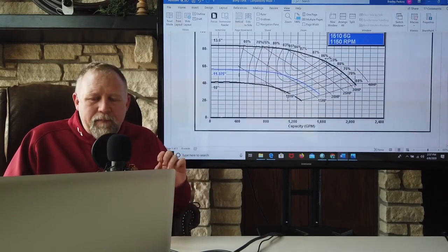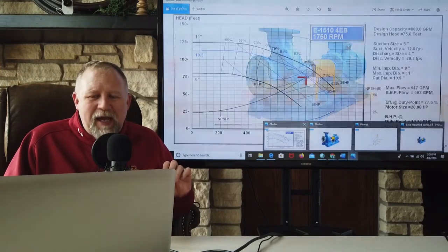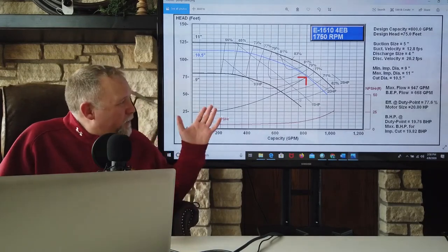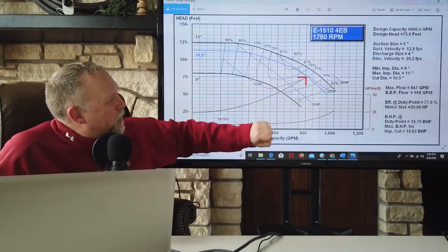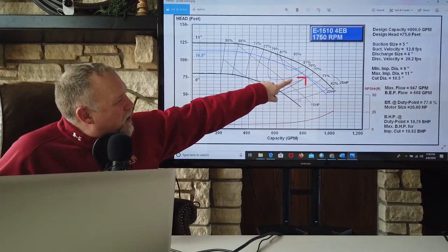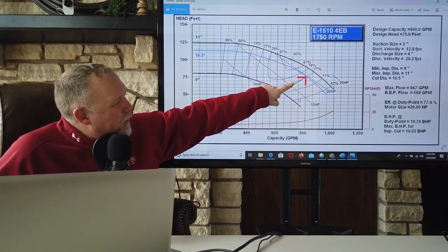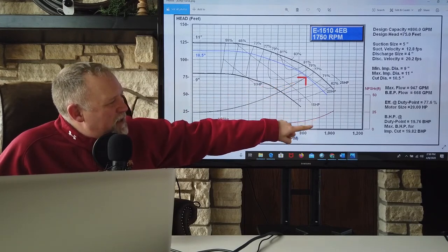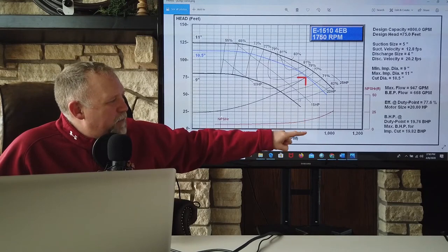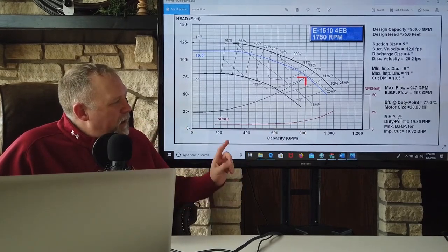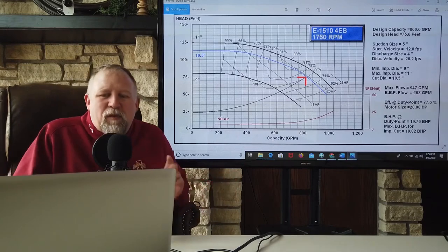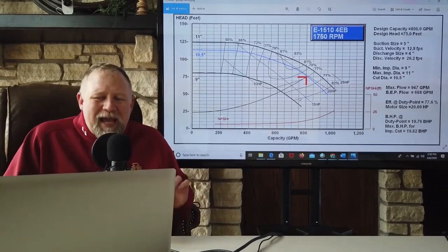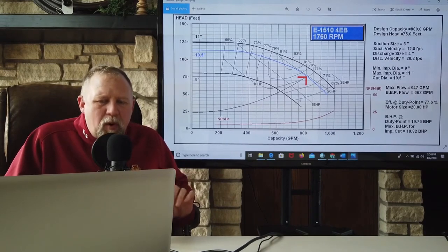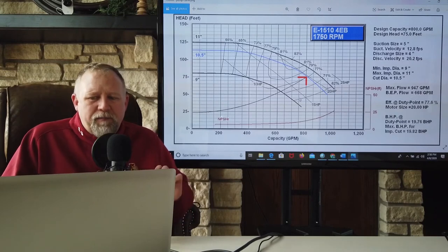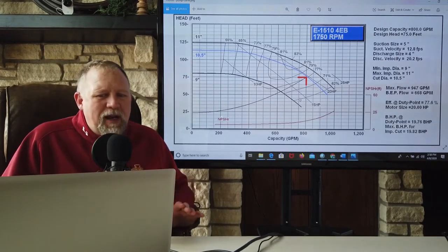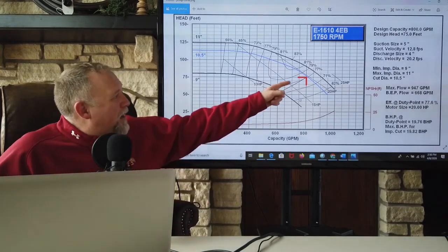Now, I do wish I had my demonstrator, all right? But here, let's go back to this other curve. Notice this curve never actually crosses the 20 horsepower point, right? Notice, see where it says BHP and max BHP for impeller. BHP stands for brake horsepower. The actual horsepower that the pump motor is consuming is brake horsepower. Brake horsepower will vary depending on where it's operating on this curve.